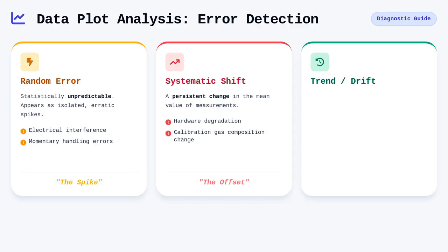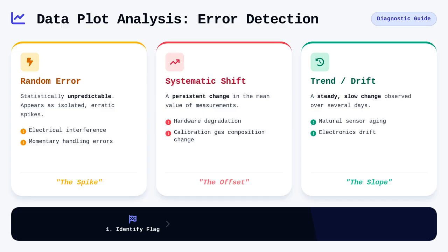If you observe a steady, slow change over several days, this is likely a trend related to sensor aging or a drift in the electronics. Addressing these issues early requires that you not only identify the mathematical flag, but also perform a root cause analysis to determine if the equipment requires a full calibration or a component replacement.